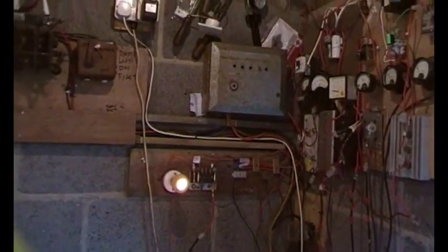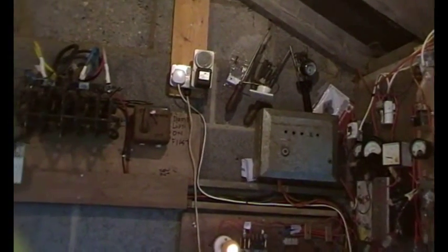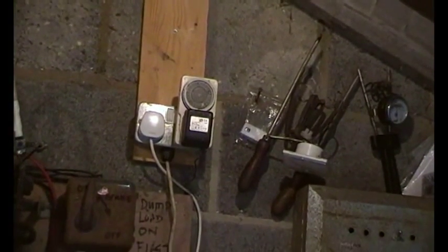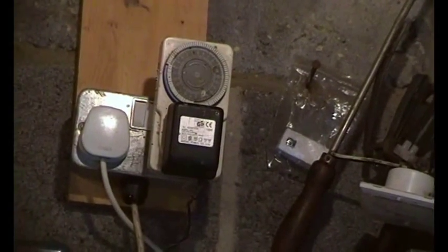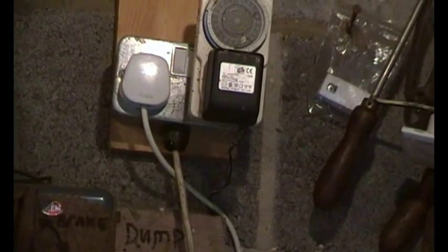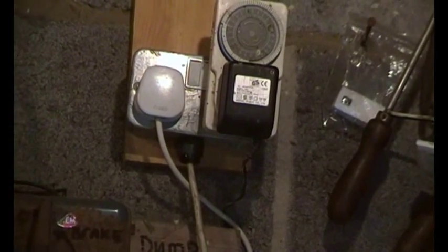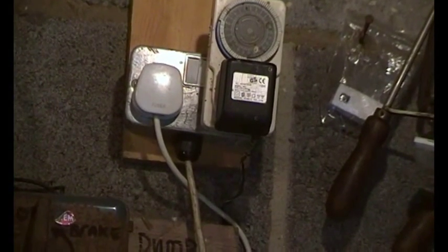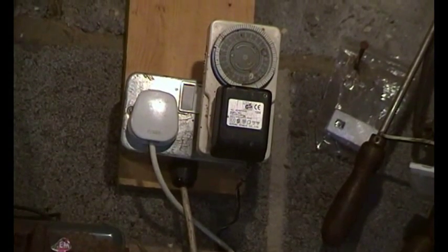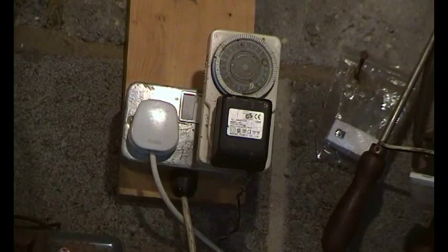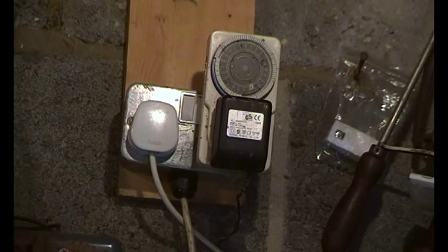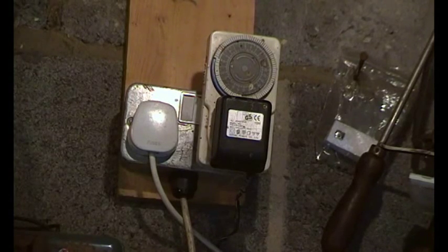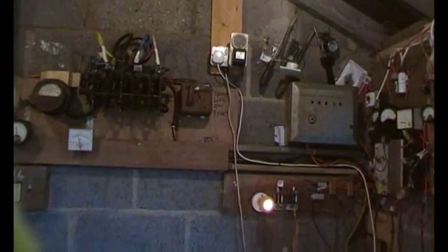Just coming up here above the tracker, we have the tracker forward and reversing timer with its power supply, and it puts power down a black and a black and white cable. Next door to it is the supply which feeds the coils in all the charge controller relays, because they're all 240 volt AC relays. The big contactor for the wind turbine dump load is 240 volt coil, so that's where the power supply comes from. It made sense at the time, probably still makes sense now.